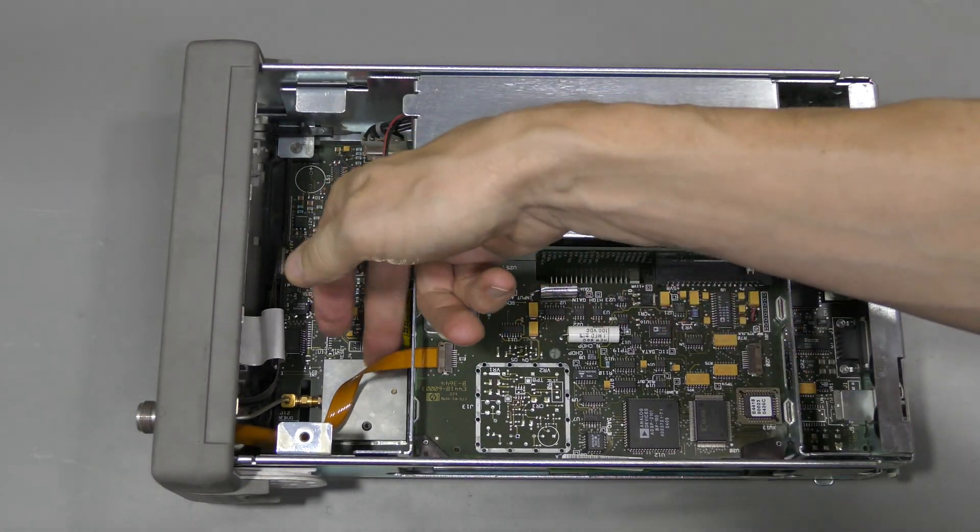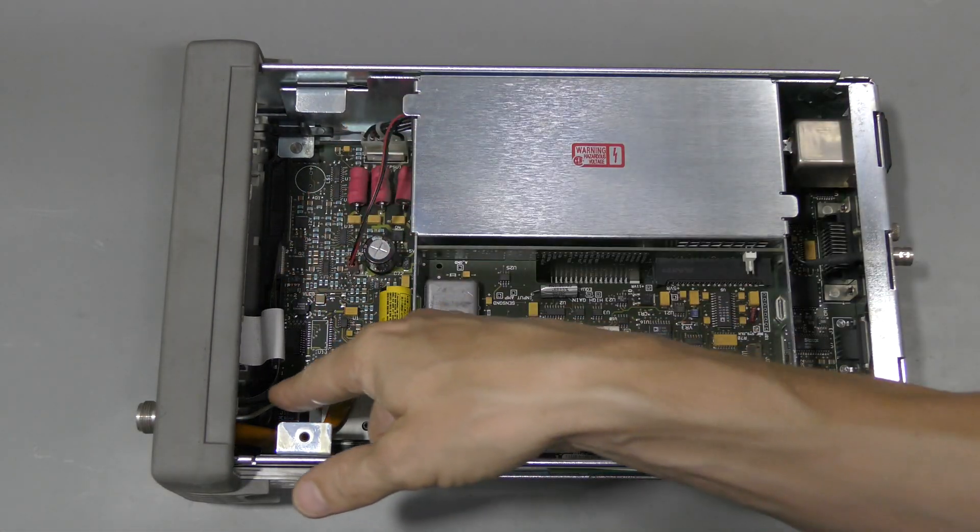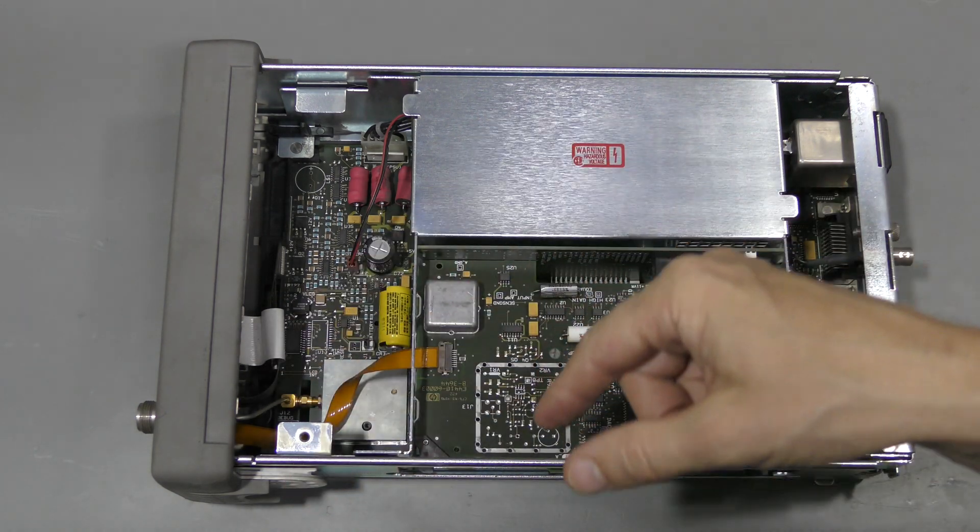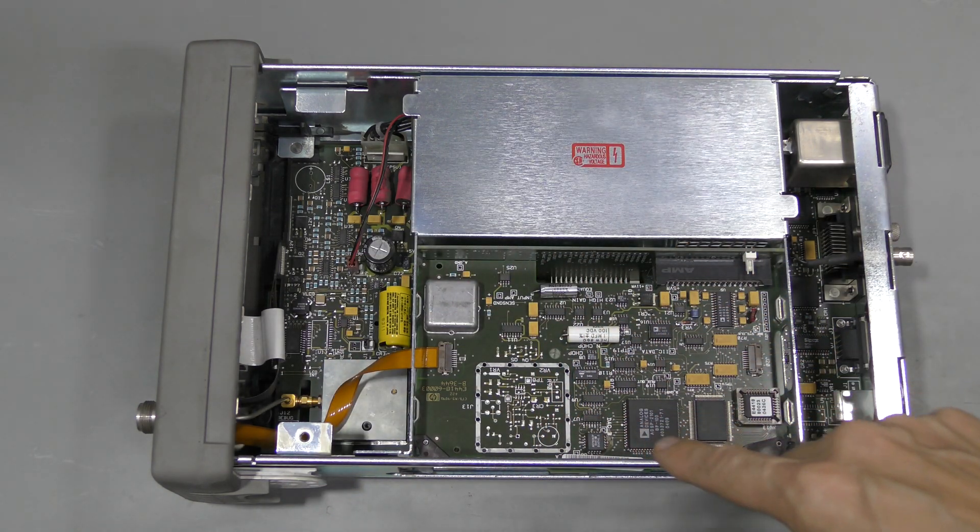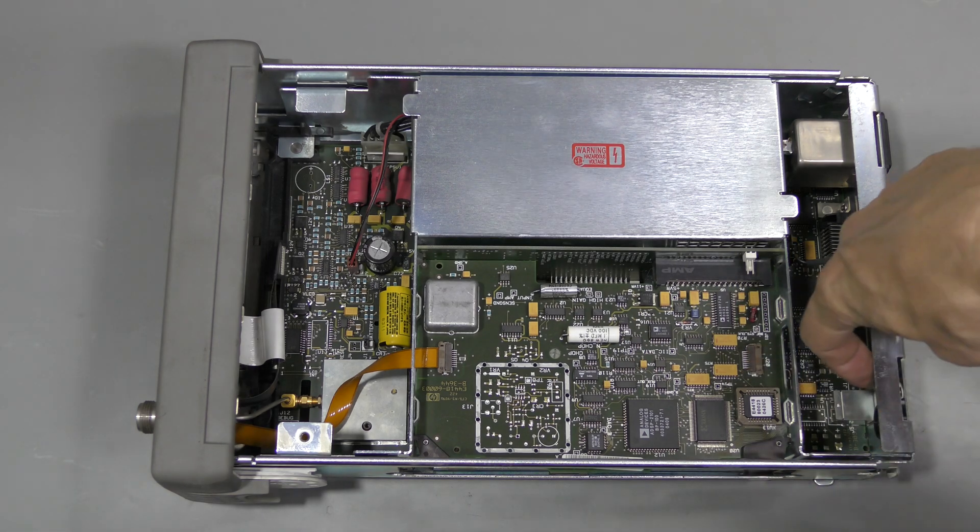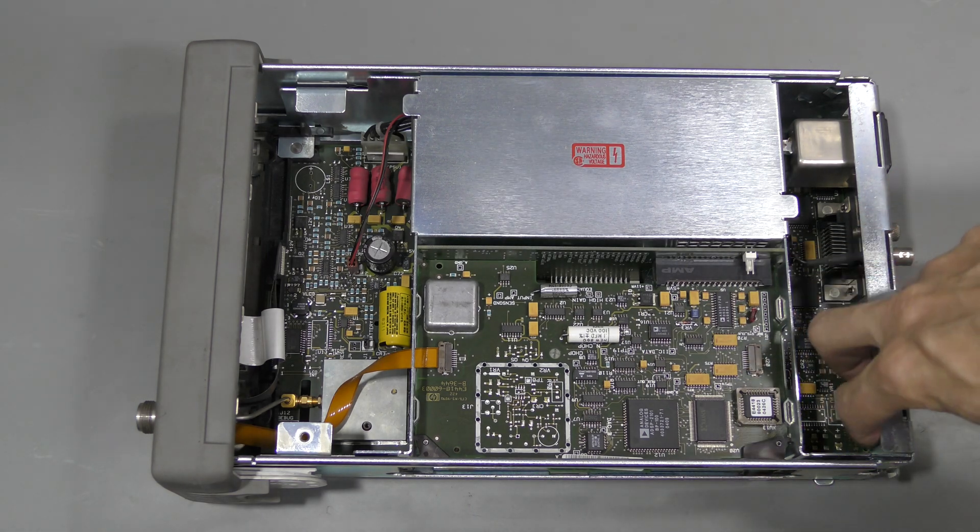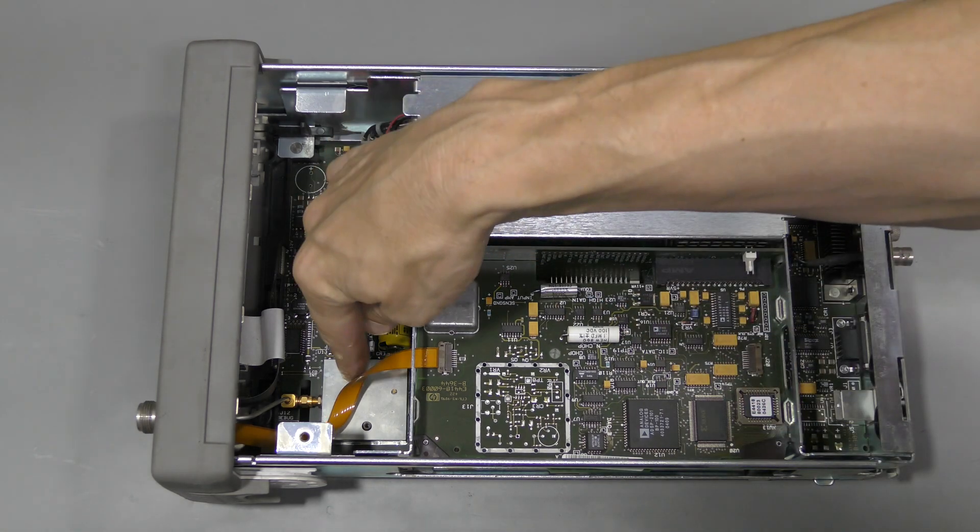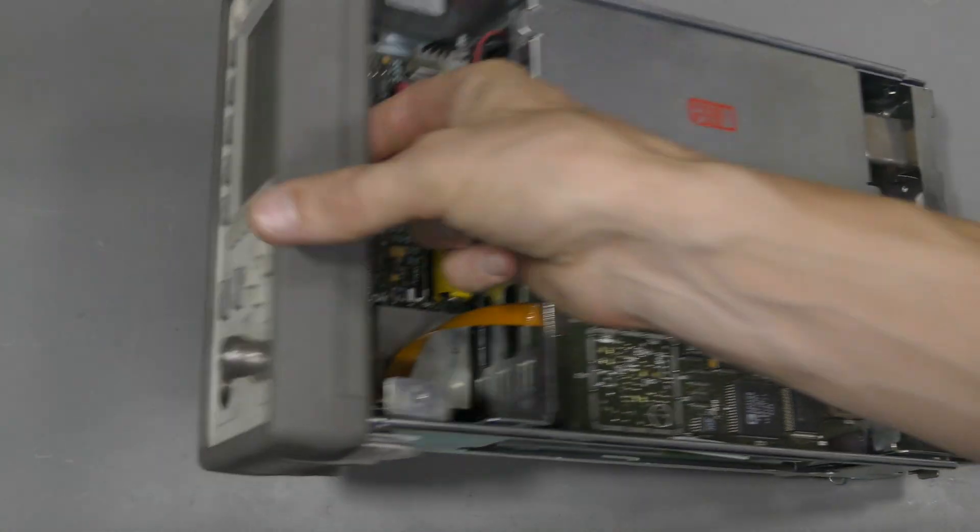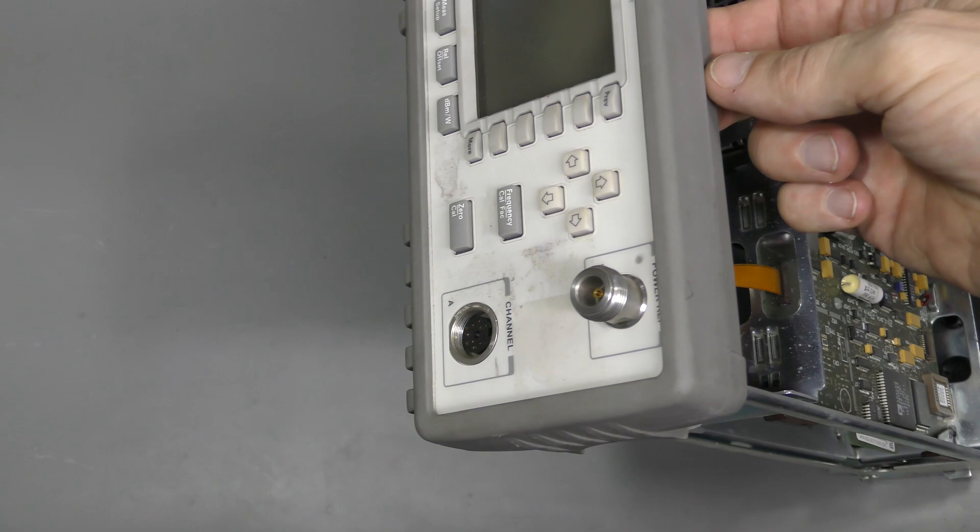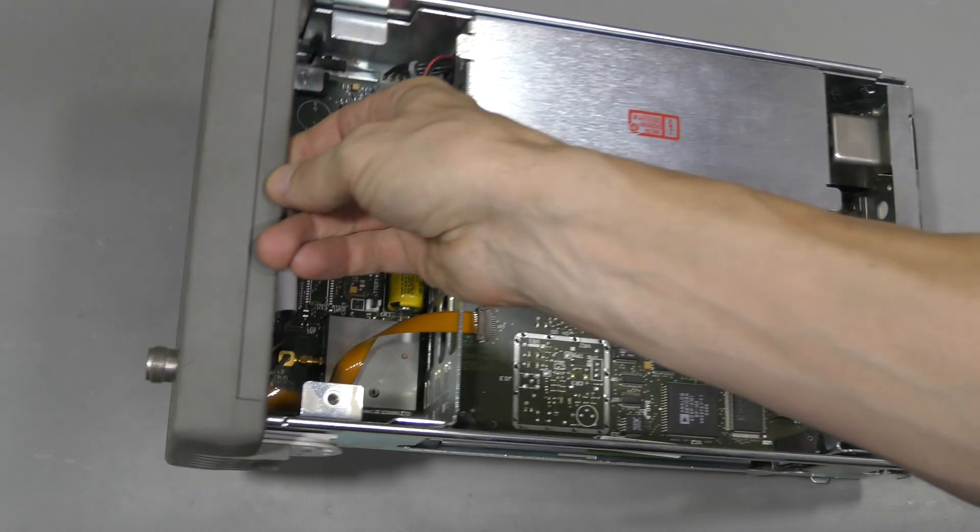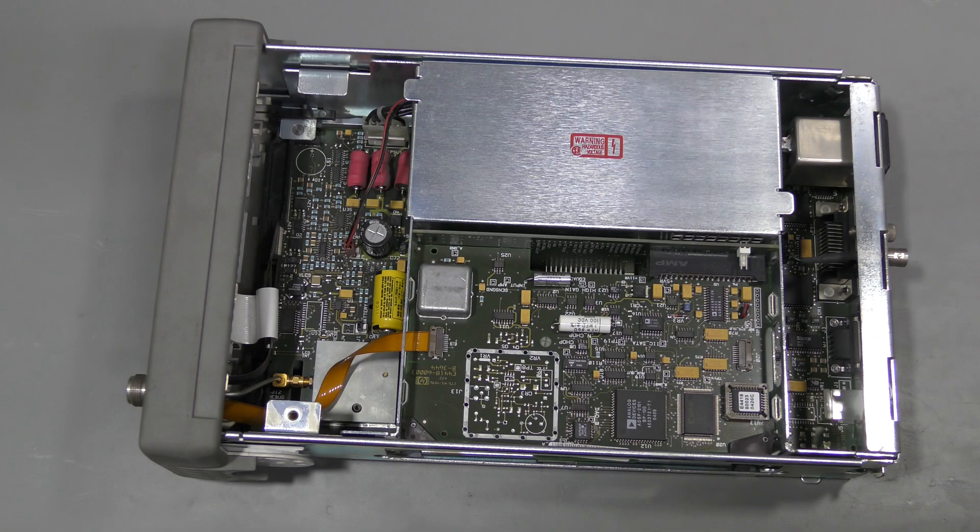And here we can see a cable from power sensor connector on the front panel. And optionally it can be installed here on the back. There are two covered holes. And this RF can is for the reference output on the front panel, which is 50 MHz and I believe 1 mW of power.